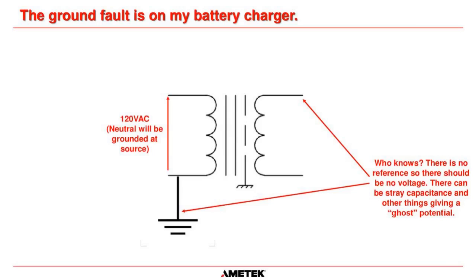The first thing I tell people, if it's an intermittent ground, the first question I ask is, has it been raining? Some DC systems get connected to analyzers out in the field, and water can get into some of the terminations going to that analyzer, and when it rains, it can cause a ground fault. So I have seen that.